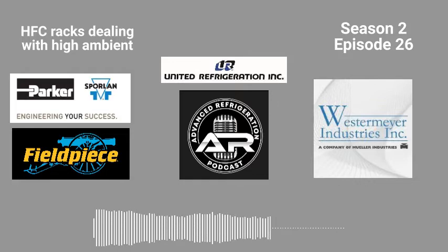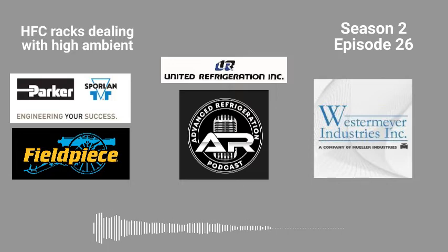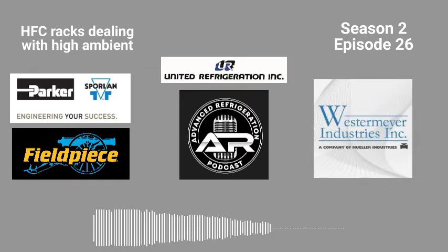Now, at this point, you have non-condensables. How do you get rid of said non-condensables? Well, there's 2 ways. You could pull the entire charge, pull a vacuum, and charge it back as a liquid. Takes time. Or you could vent it off into a recovery tank several times. On your paperwork, make sure that you write down that you recovered non-condensables. It is still illegal for you to just blow off what you think might be air, and there's no way to really tell whether you are letting air out or letting refrigerant out. I usually go till I see liquid coming out into the tank.